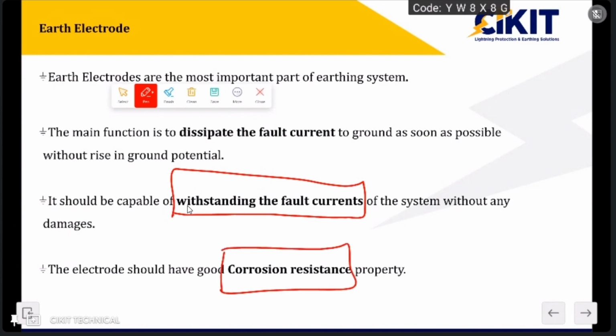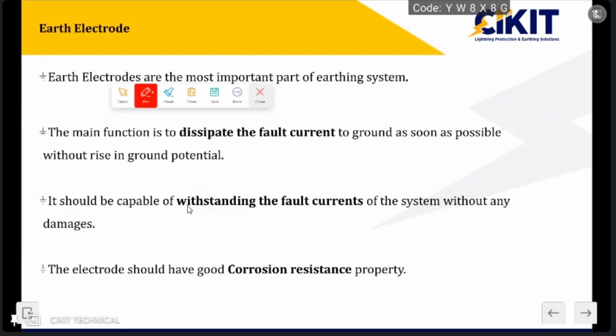Everyone knows that aluminum is a very good conductor, and for all transmission networks we use aluminum. But for earthing, we won't use aluminum. Even though aluminum is a very good conductor, because of its corrosion resistance property we are not using aluminum for earthing applications. So one of the important properties of an earthing conductor should be good corrosion resistance.